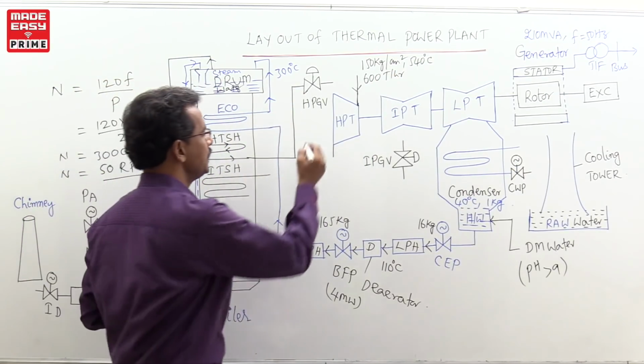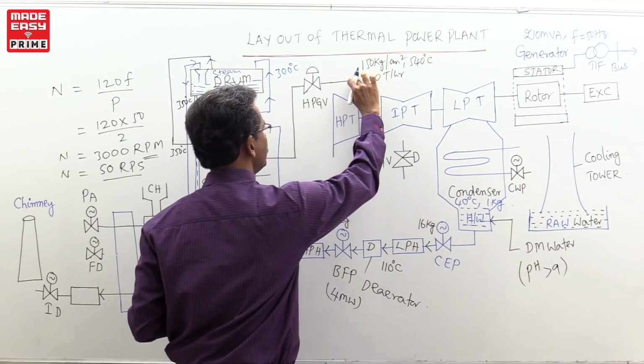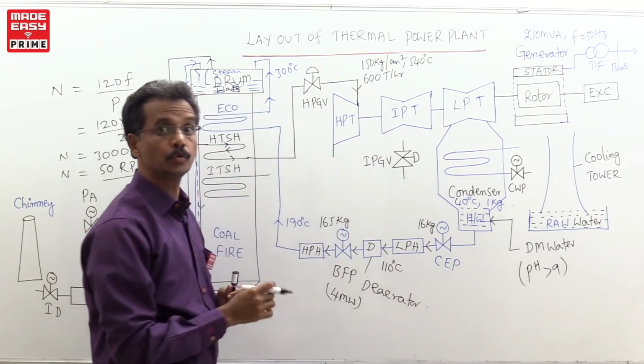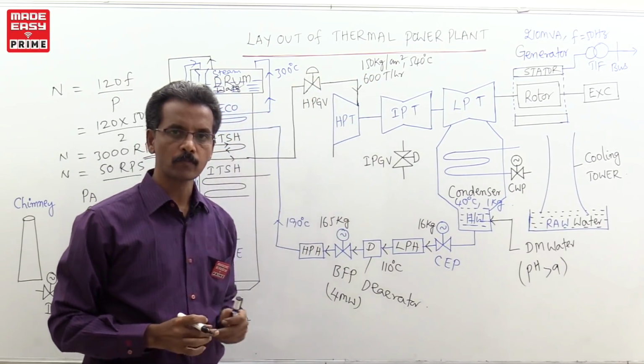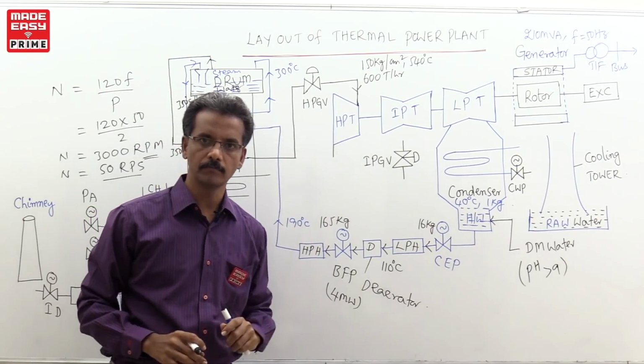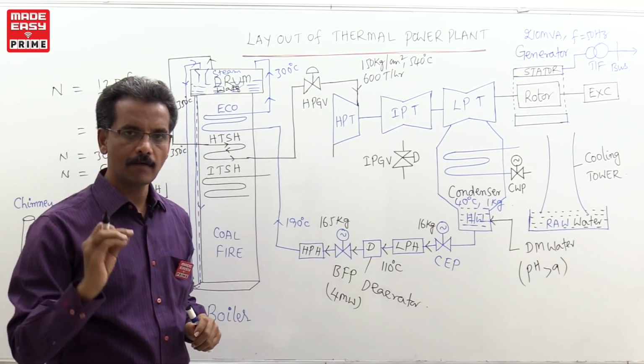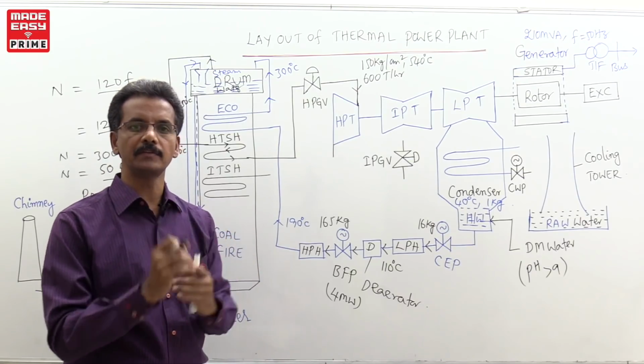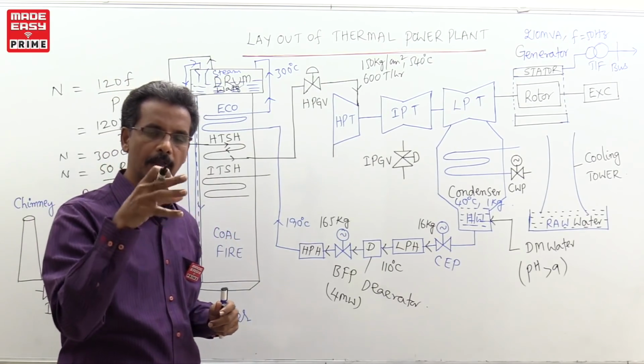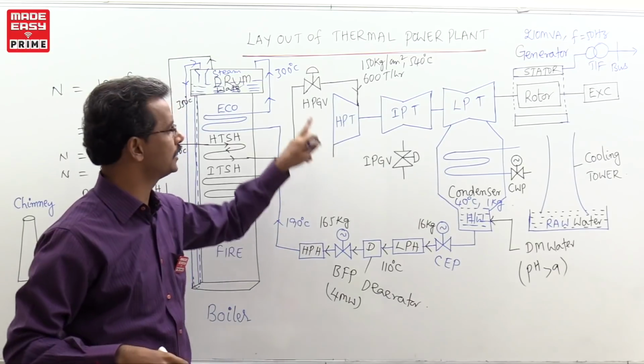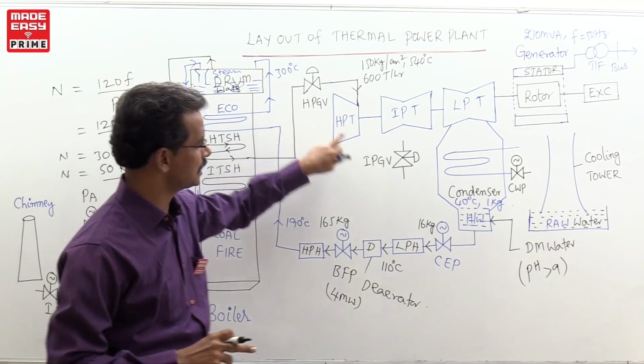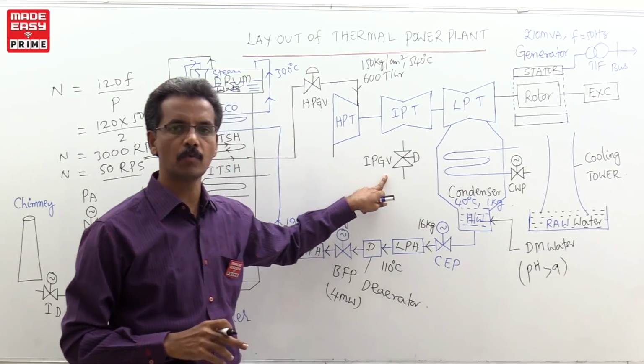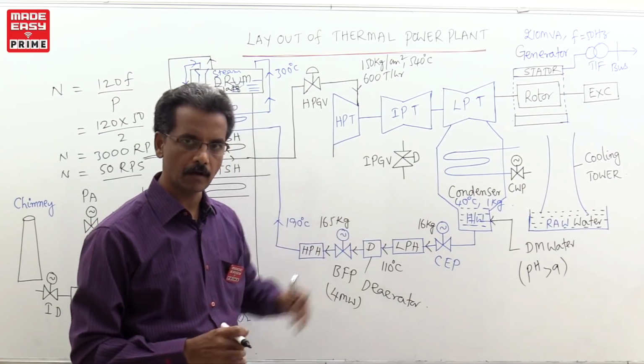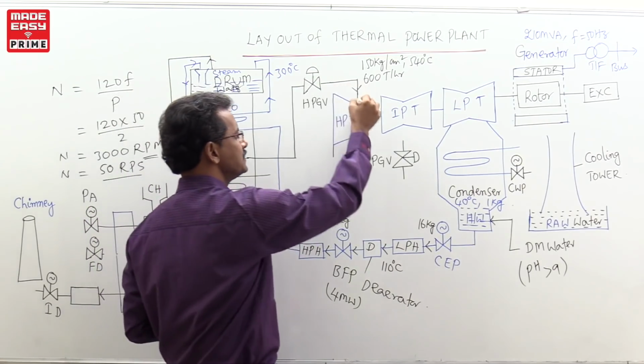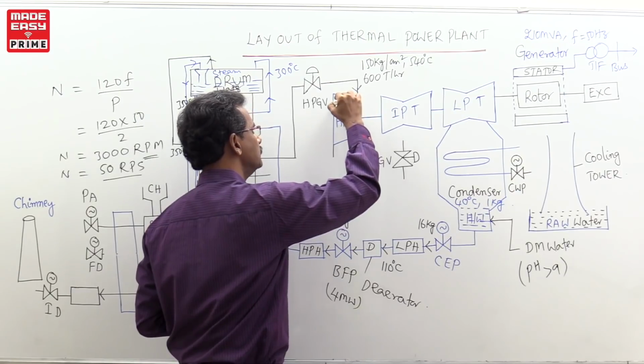So this steam now enters into the turbine through the governing valve. This is what is called the high pressure governing valve. This governing valve is used to control the speed of the turbine by controlling the steam flow rate into the turbine. This is one, and there is one more governing valve, called the intermediate pressure governing valve. Right. Now, the steam admitted into the turbine will be expanded.